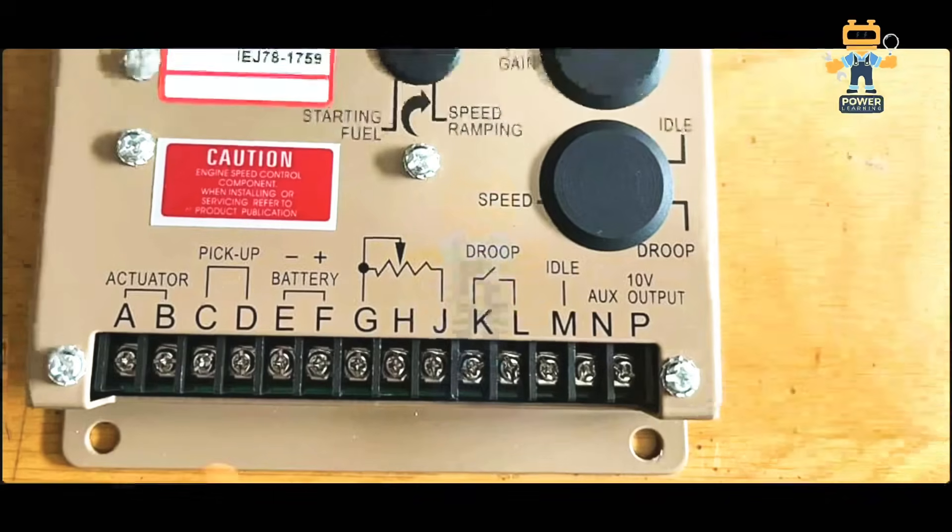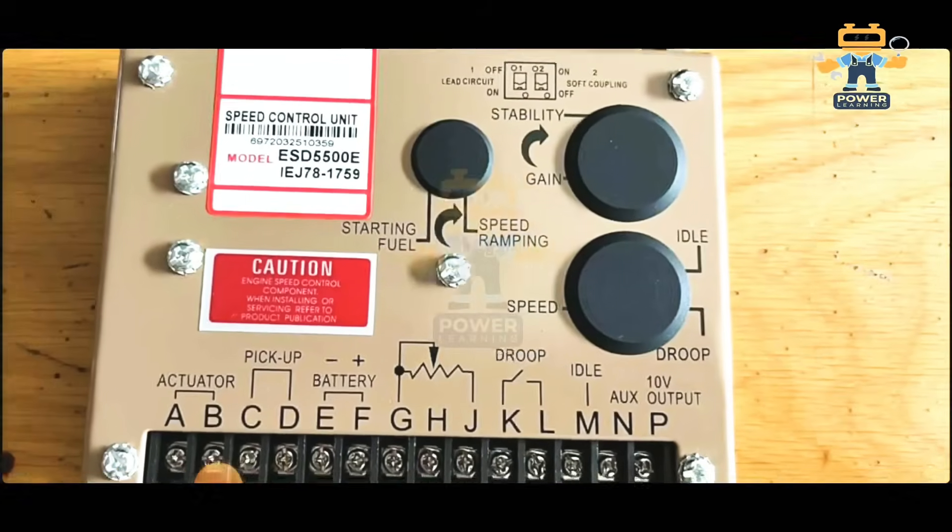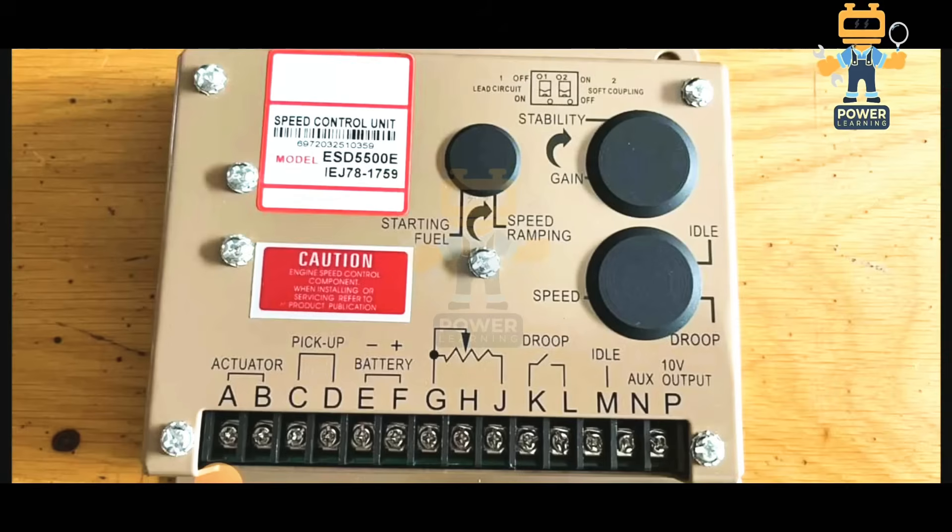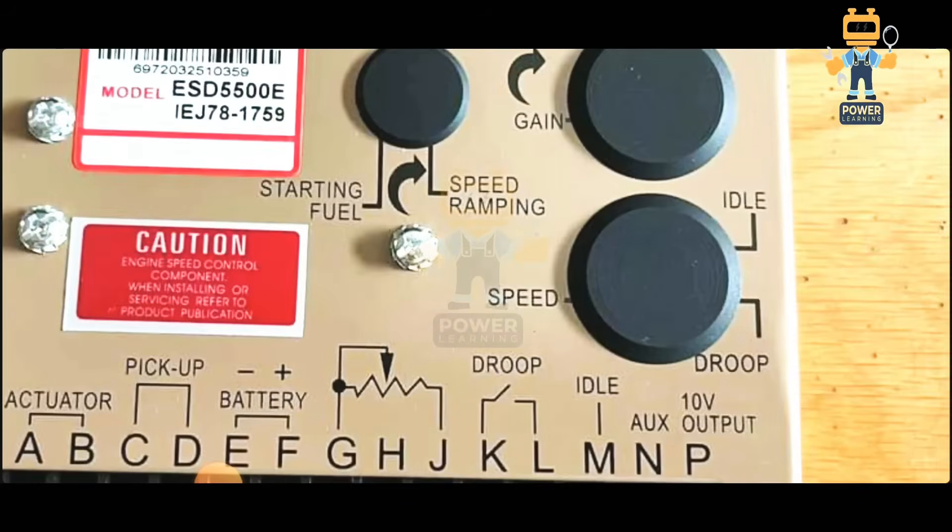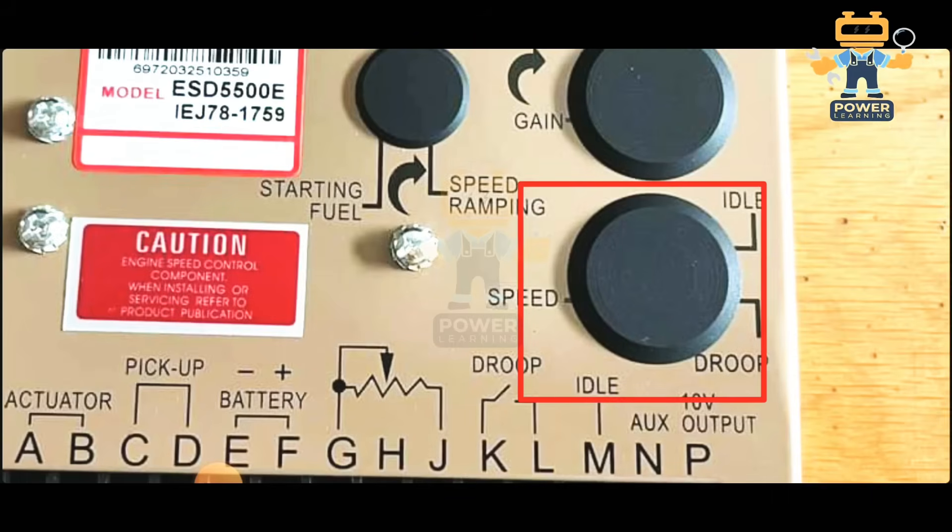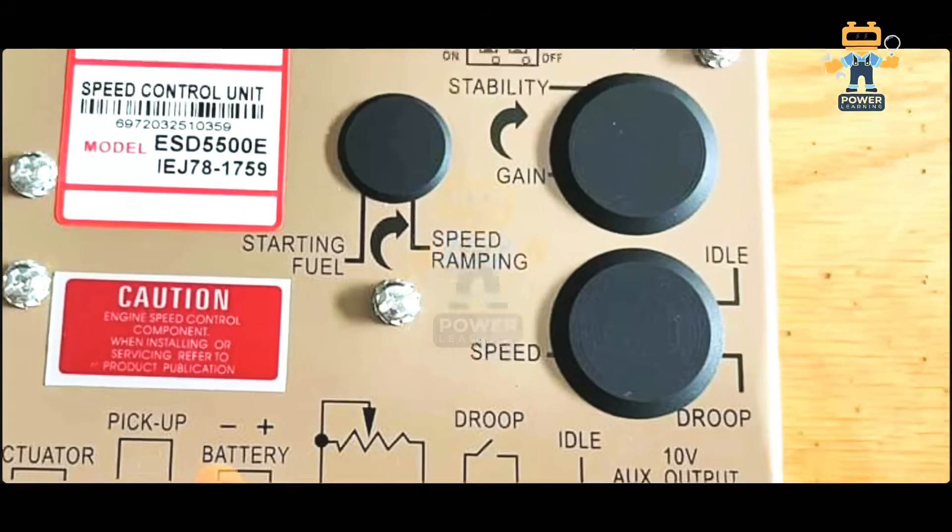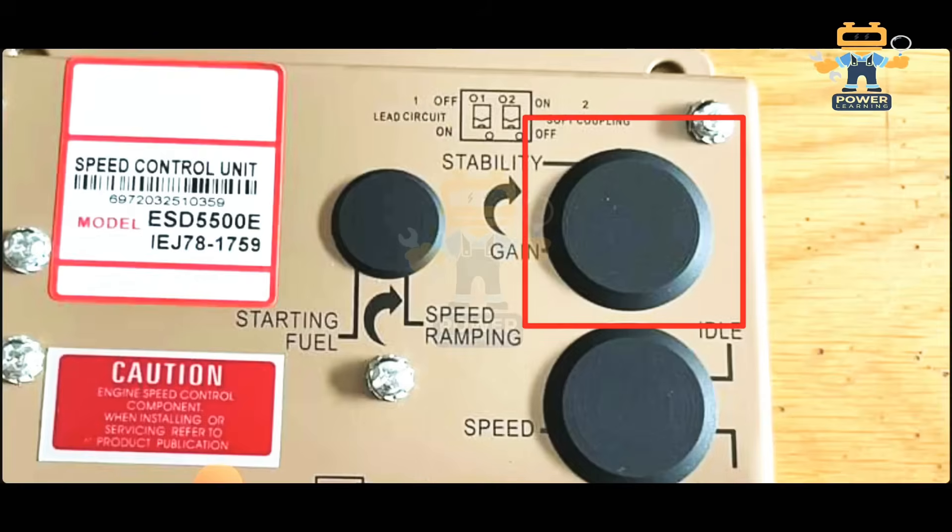After that, here if you see we have this black cover. If you remove it, you will find inside there is a potentiometer to adjust the droop and idle speed. Here on this above cover, if you remove it, you will set engine gain and stability - there are two potentiometers inside, so from here you can stabilize the engine speed if there is variation.